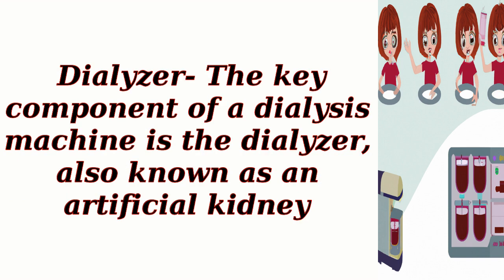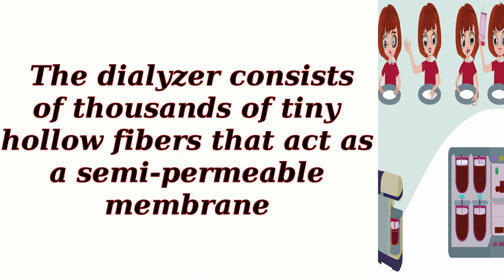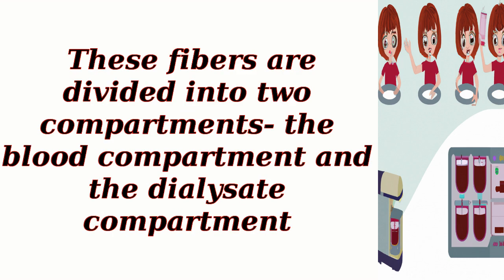Dialyzer: the key component of a dialysis machine is the dialyzer, also known as an artificial kidney. The dialyzer consists of thousands of tiny hollow fibers that act as a semi-permeable membrane. These fibers are divided into two compartments: the blood compartment and the dialysate compartment.